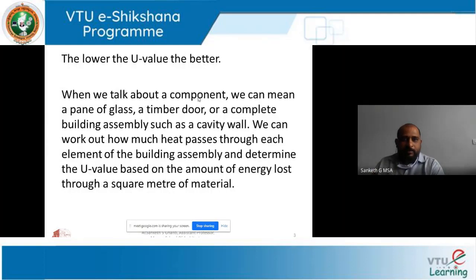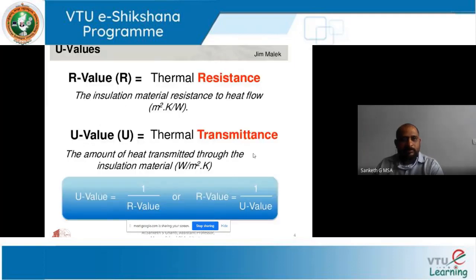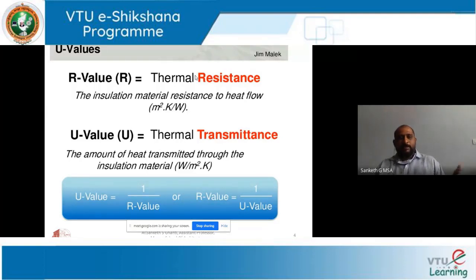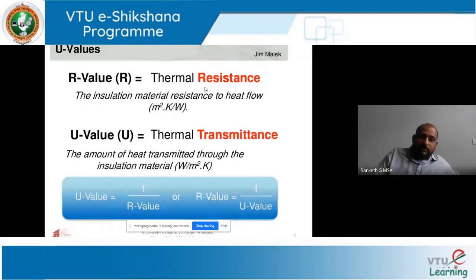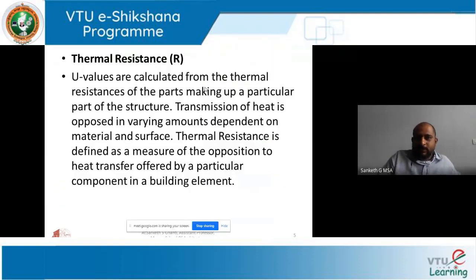The lower the U-value, the better. When we talk about the component, we can mean a pane, glass, or doorway. R-value is the opposite of U-value. U-value is thermal transmittance — the heat that is passing through. R-value is nothing but resistance; it is stopping the heat. In equation form, U-value is equal to 1 divided by R-value. Please note this down. R-value is thermal resistance and U-value is thermal transmittance.